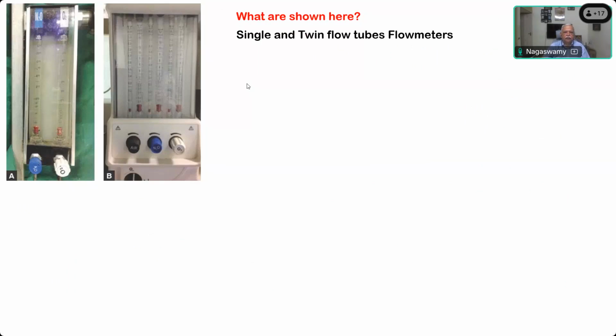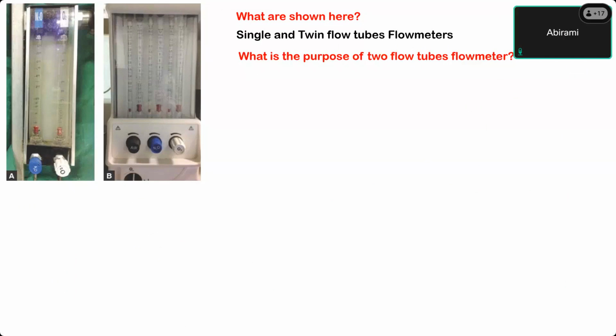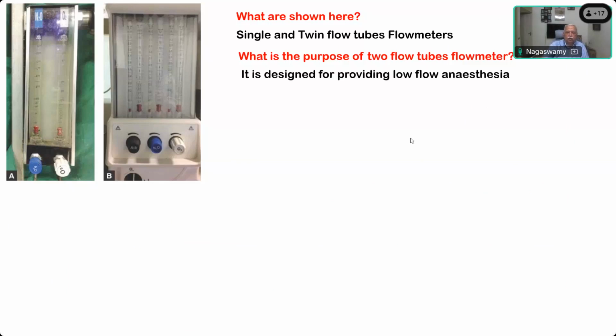Okay. So what is the purpose of a two flow tube flow meter? It gives access to low flow graduations and high flow divisions. You require a low flow tube for low flow anesthesia. So two flow tubes are nowadays incorporated in the anesthesia workstation for facilitating low flow anesthesia. The first tube is divided in fractions up to a maximum of 1 liter, whereas the second tube starts from 1 liter and goes up to 10 or 12 liters.